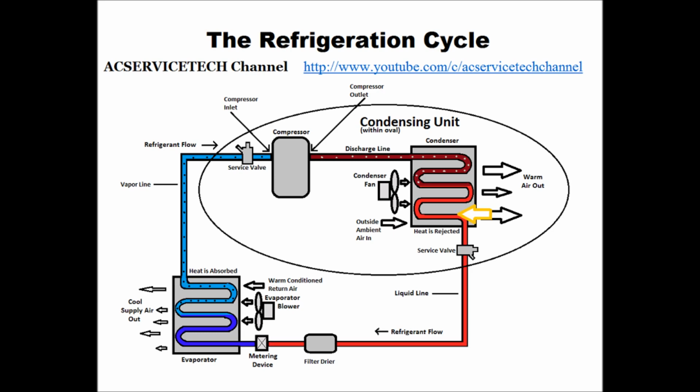The condenser is where subcooling takes place, and subcooling is the temp decrease in liquid form in the condenser, to where it comes out past the service valve. That is subcooling. There's only one spot where there's liquid in the condenser coil, and it's after the saturated state. Where it comes out, we always take a temp reading right next to the service valve, because that's where we can get an accurate pressure reading.